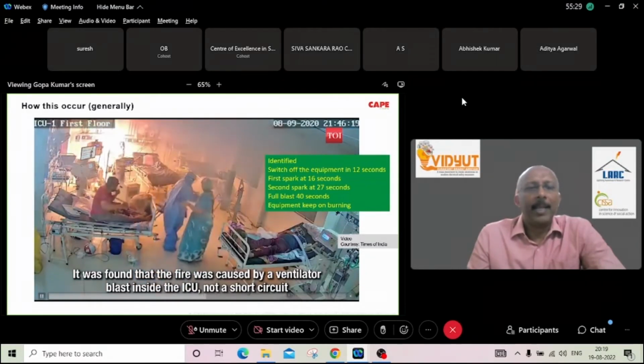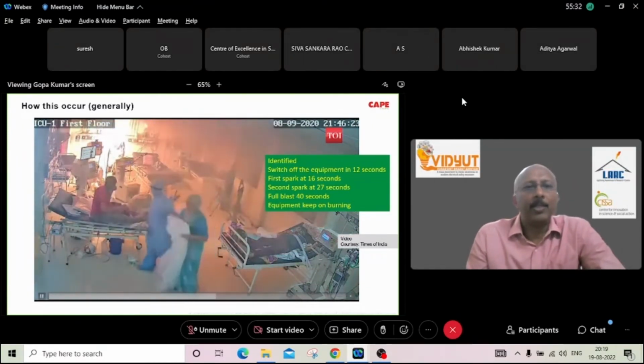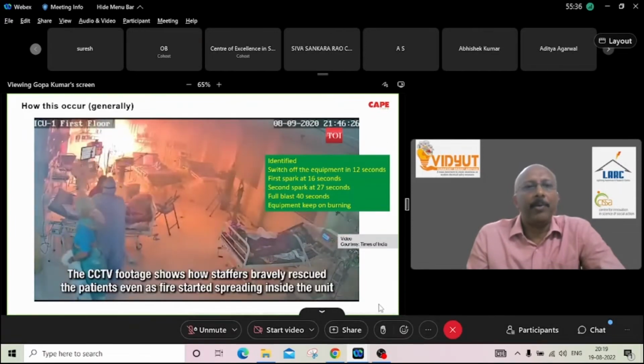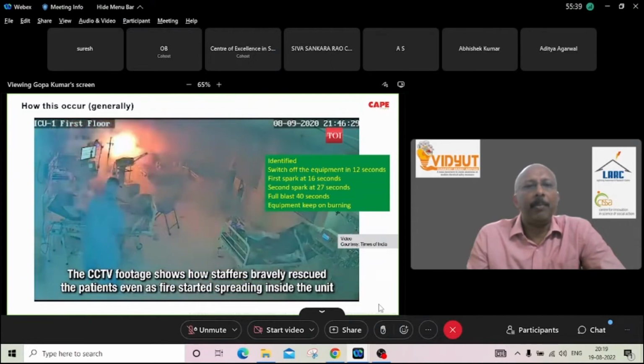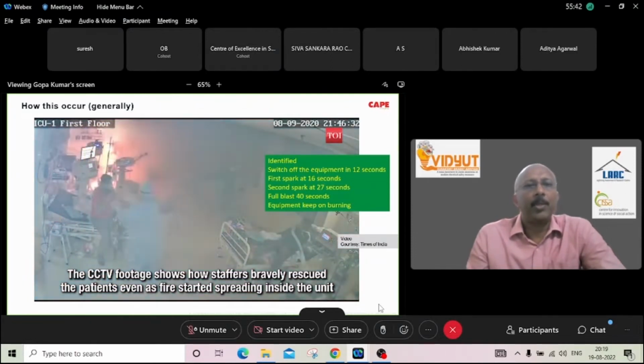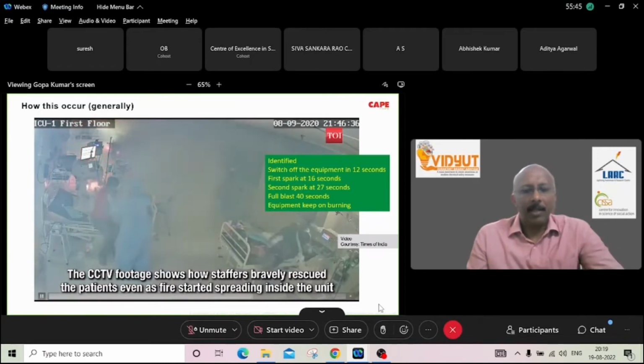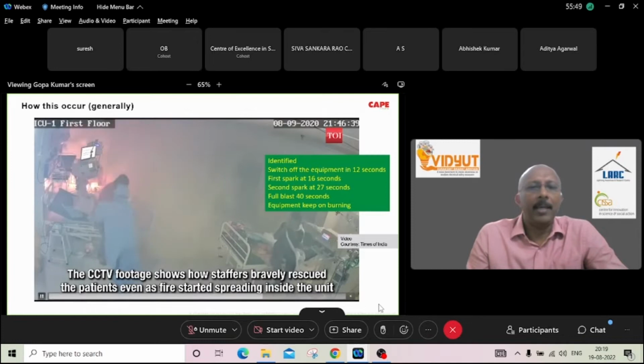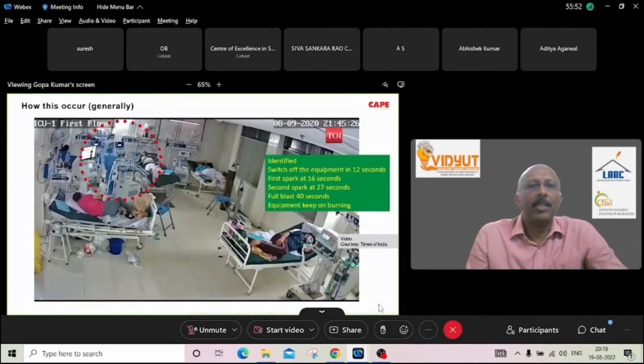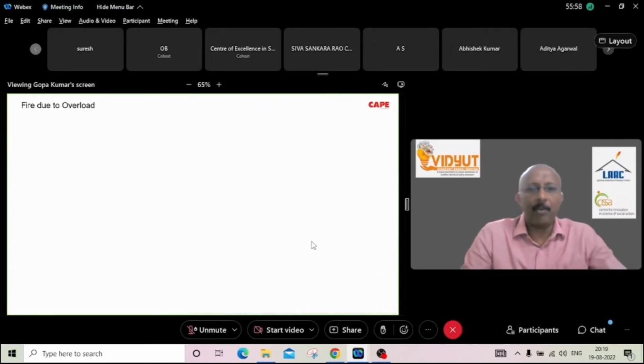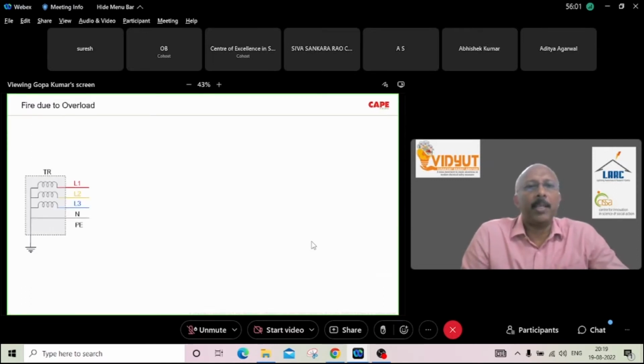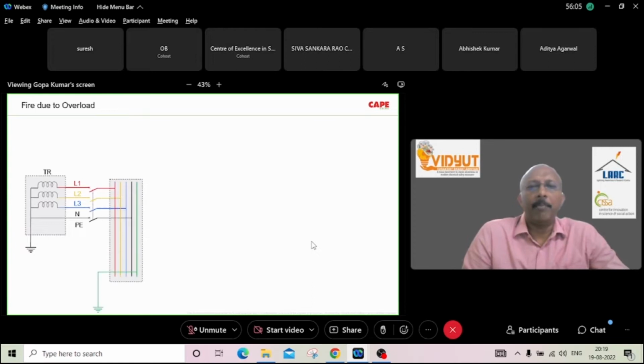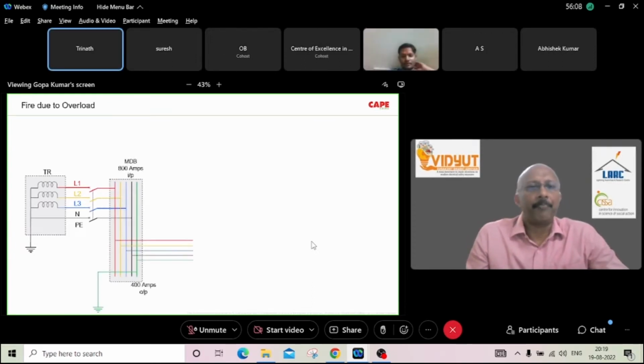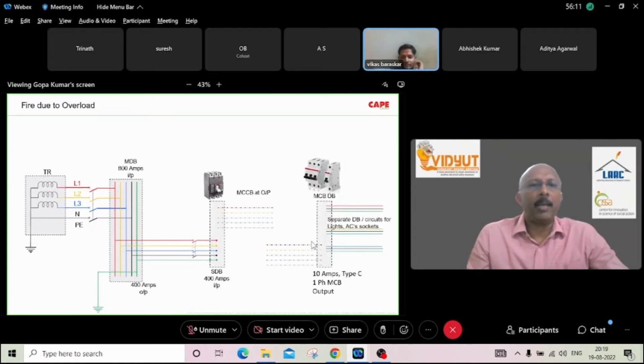That is one part. But the second part, which an electrical engineer should always think about, is why this equipment is catching fire. What happened to the protective device? Before catching fire, the MCB should trip. The purpose of the MCB is to trip so that there is no fire accident. But after all these accidents, what we generally hear is that accidents are due to overload, because the wiring is too old. The wiring is designed for connecting 10 equipment, but the client has connected more, and because of overload, the fire has started.